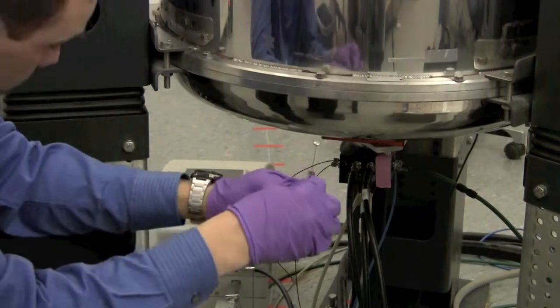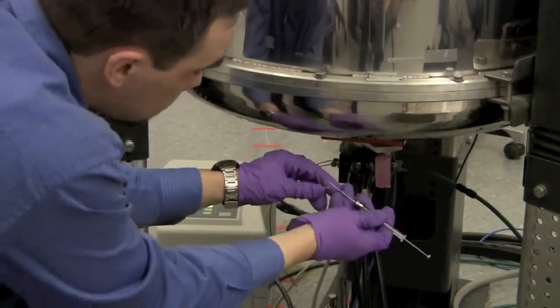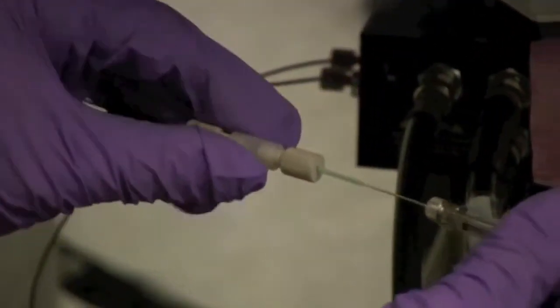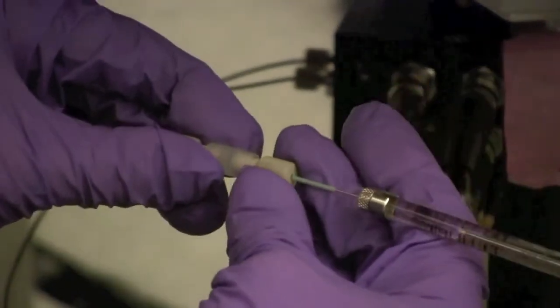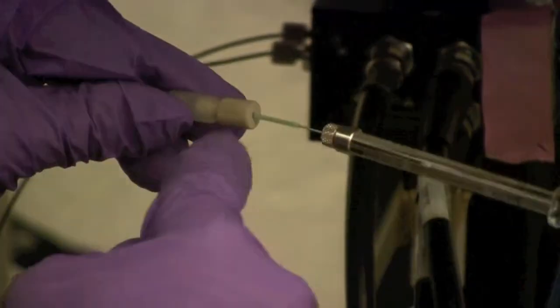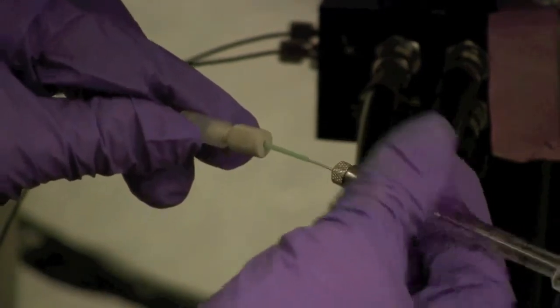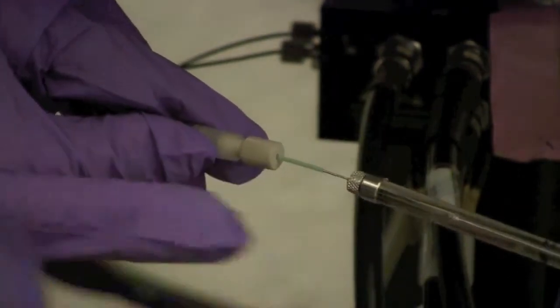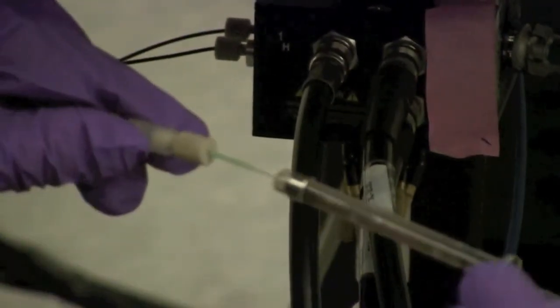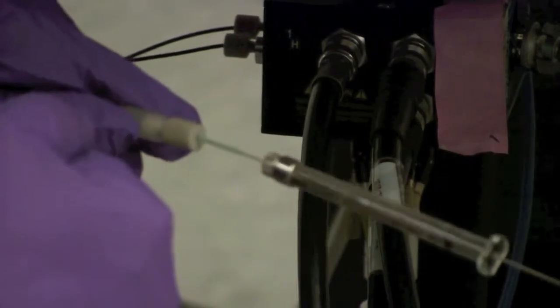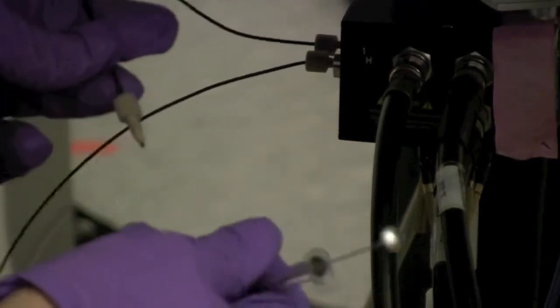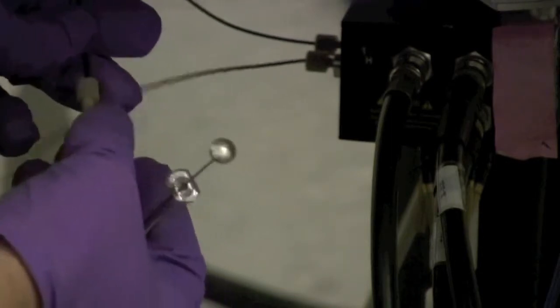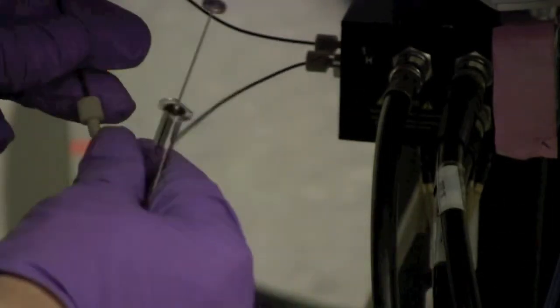Okay, so now what we're going to do is we're going to put the syringe into the inlet here. You want to push it down until it hits the bottom, and then carefully you want to tighten it. Tightening this connection here will make it so the syringe is sealed, and so when you push in the sample it doesn't come back out. That would be bad. So now we're going to push the sample into the probe, and if you have 25 microliters, that should be enough to fill the probe but not exit out of this outlet here. If you want to be extra careful to recover your sample, you can put a recovery vial on here at this point. In this case, I'm not too worried about it, so we don't need to do that.